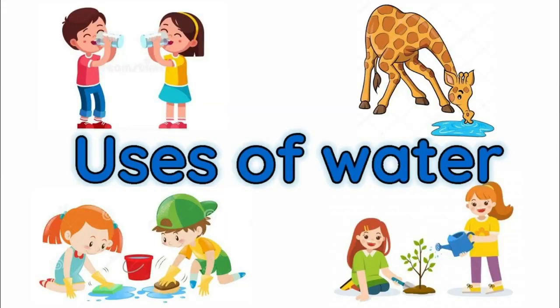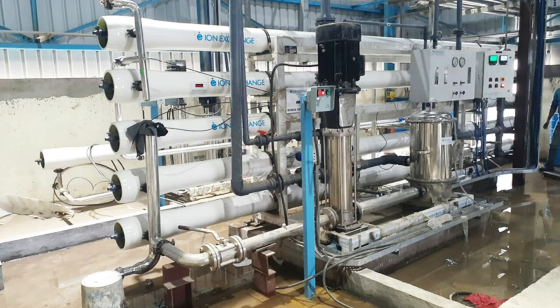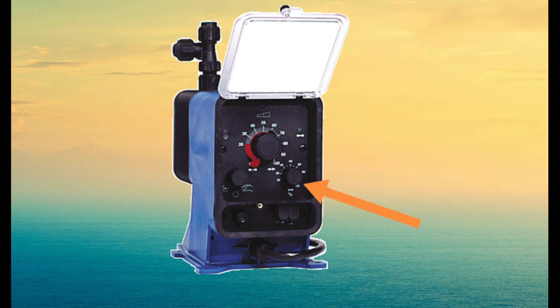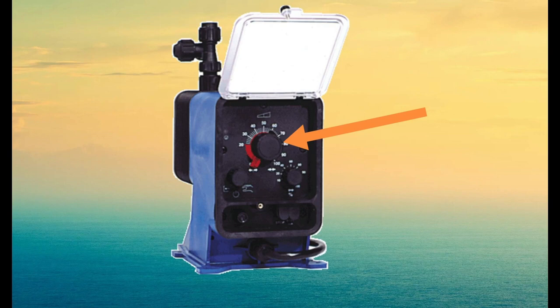Now let's see how to maintain the dosing of all these chemicals for an efficient and reliable RO plant. There are two ways to adjust the chemical dosing. The first way is to increase the dosing pump speed and the second way is to increase the dosing pump strokes.